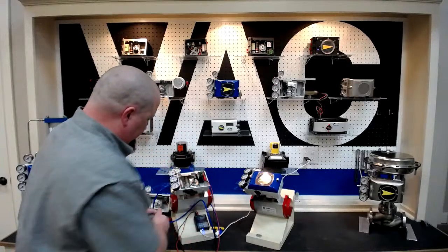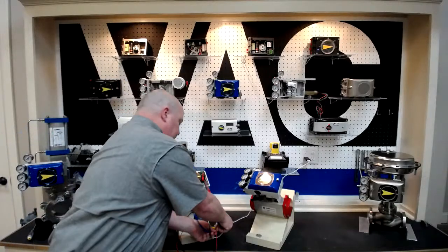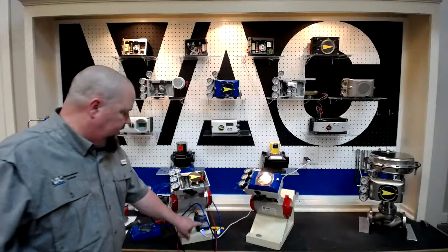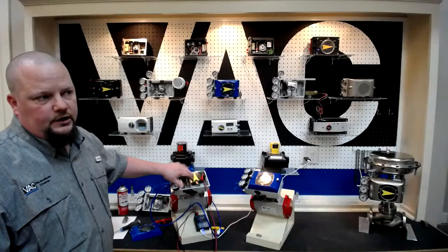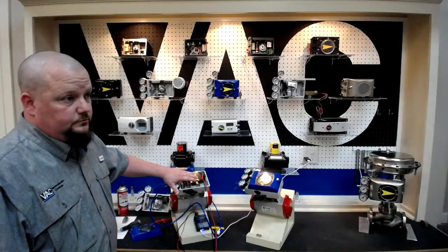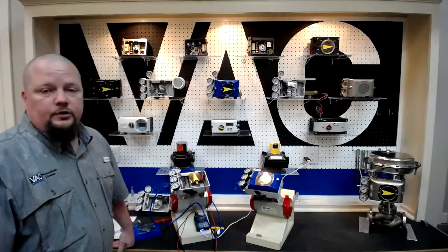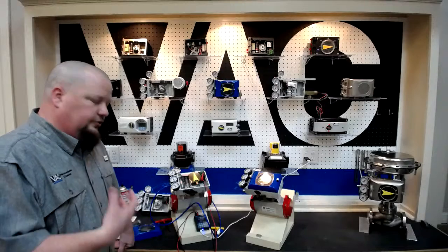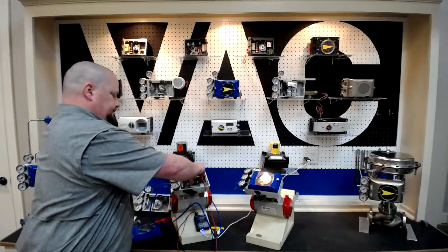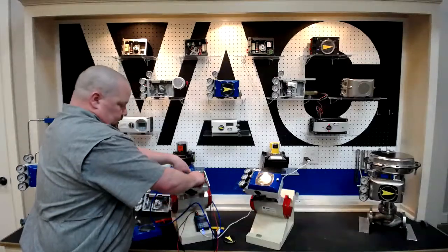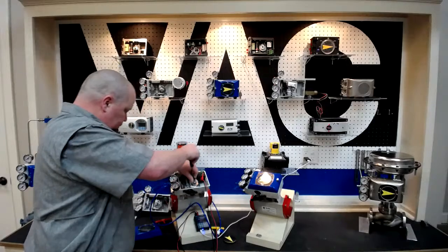If the cam is not set and tightened properly, at 4 milliamps everything is fine, but as soon as we start increasing signal, a 1 milliamp increase to 5 milliamps, and it drives all the way open. And you go back to 4, and it will not stroke because there's no feedback to the cam, and it's going to stroke very slowly. These are all, like I said, the most common issue is a cam setup issue.